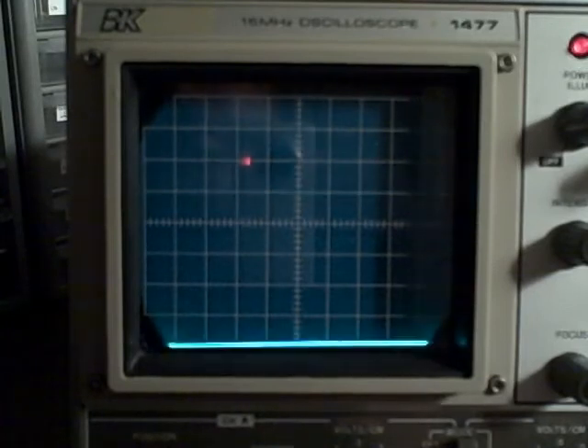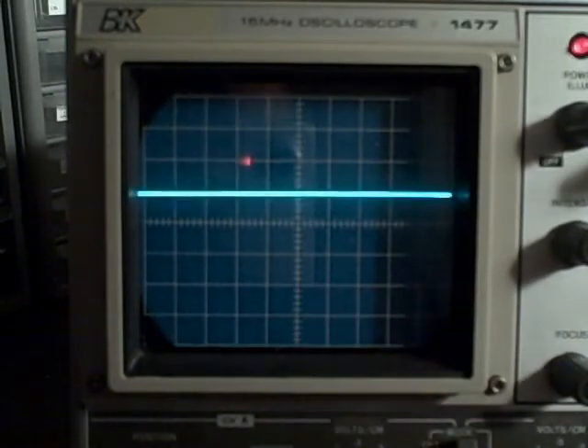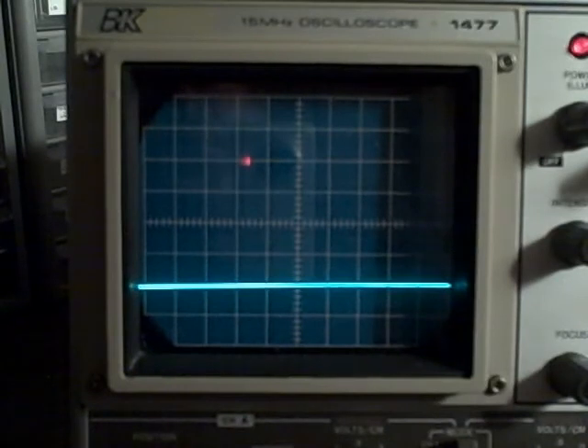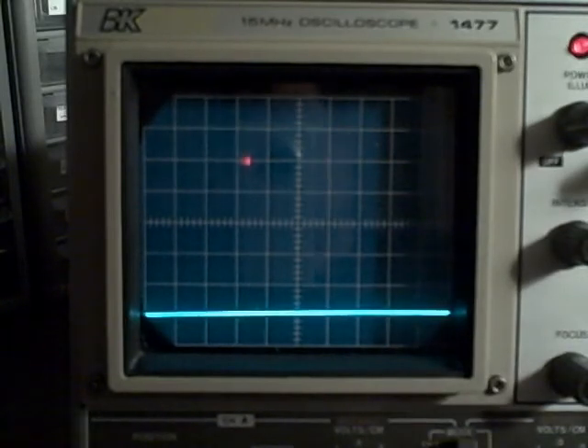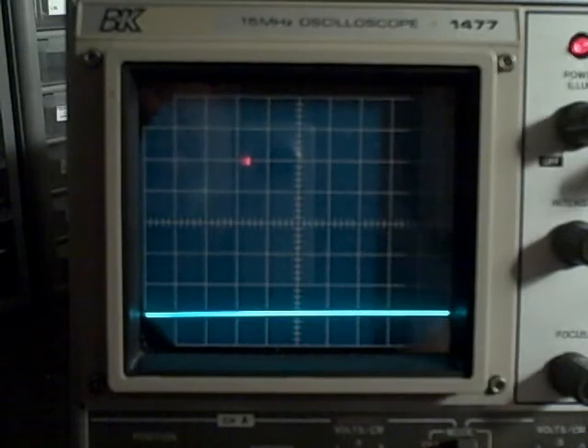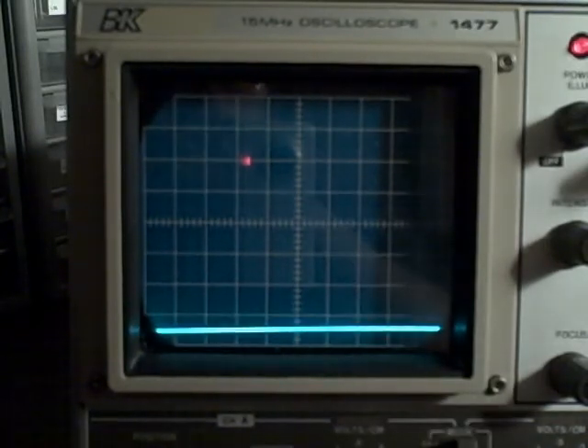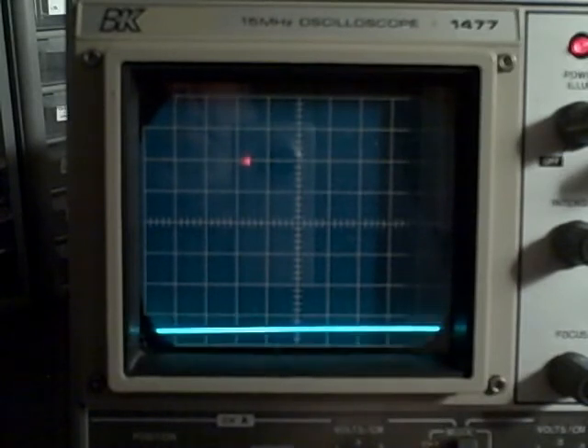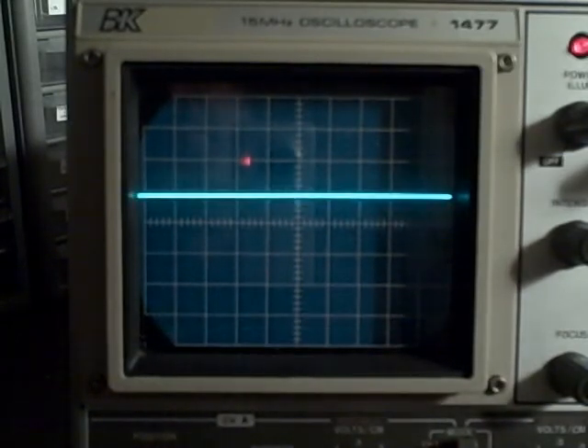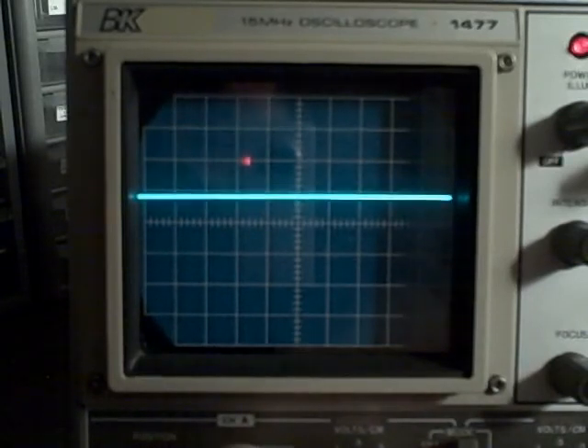Okay, we're going to spot check the 2 volt per division right at the moment. We've got 10 volts coming in, and we have 10 volts showing. Okay, if we go to 5 volts per division, that's 2 divisions, that's 10 volts. And then 10 volts per division, that would be 1 division. I can't go to 100 yet. We'll go to 20 volts per division, and then we'll go to 100. Let's make sure we're zeroed. 0 looks good, and we go to 100, and we see ourselves up at 5 times 20 would be 100 volts. All right, let's take a look at channel 2, or channel B.